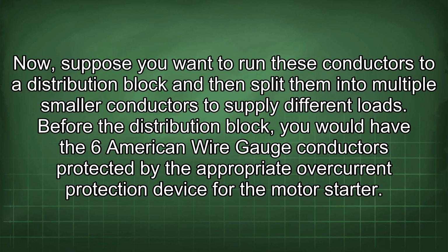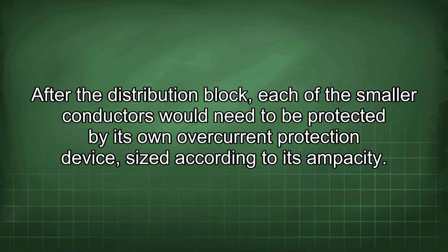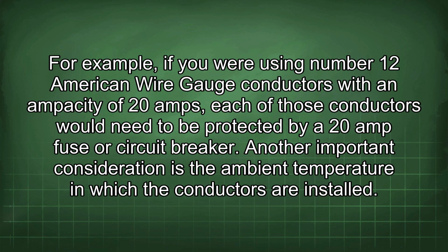Now, suppose you want to run these conductors to a distribution block and then split them into multiple smaller conductors to supply different loads. Before the distribution block, you would have the 6 American wire gauge conductors protected by the appropriate overcurrent protection device for the motor starter. After the distribution block, each of the smaller conductors would need to be protected by its own overcurrent protection device, sized according to its ampacity. For example, if you were using number 12 American wire gauge conductors with an ampacity of 20 amps, each of those conductors would need to be protected by a 20-amp fuse or circuit breaker.